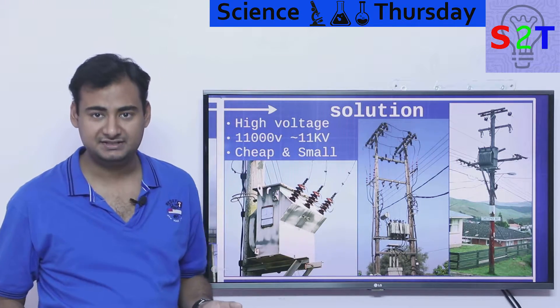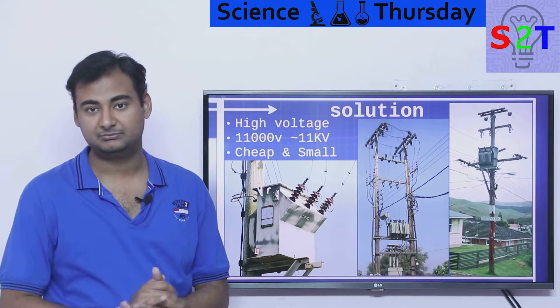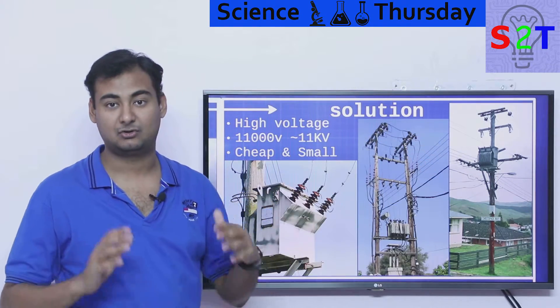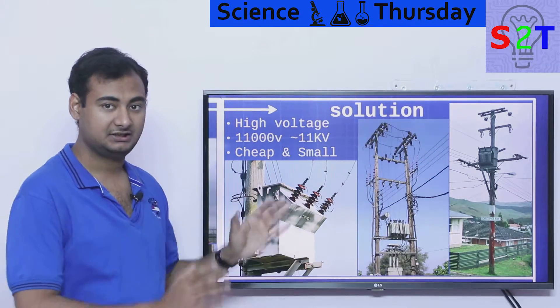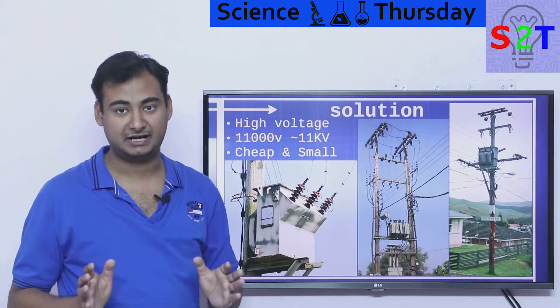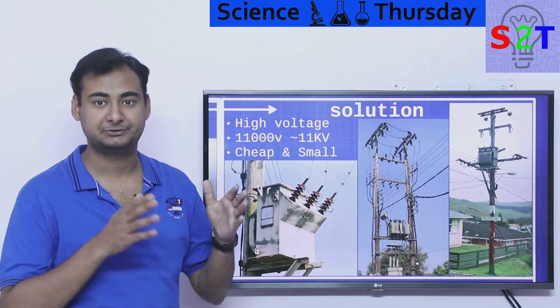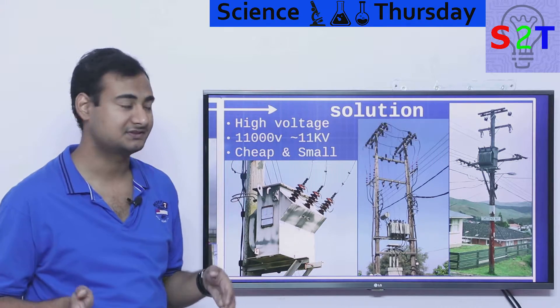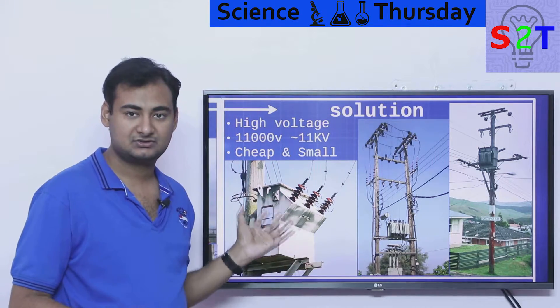It also means how high you have to keep it. You have to make sure that if a giant metal truck or garbage truck has to go below a conductor, electricity should not get excited and jump on it. 11 kV has been chosen, and there are certain benefits. 11 kV is not too high, so the transformers that we need to step down that 11 kV are not that big nor expensive. This is why we built this miniature substation that is on a pole.